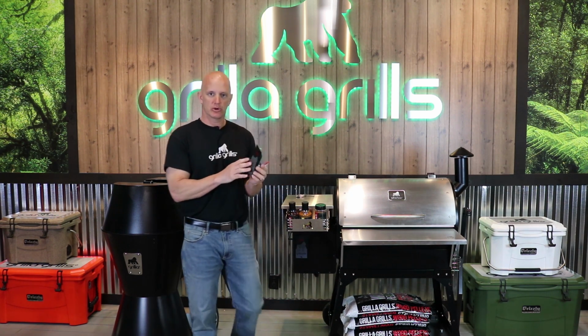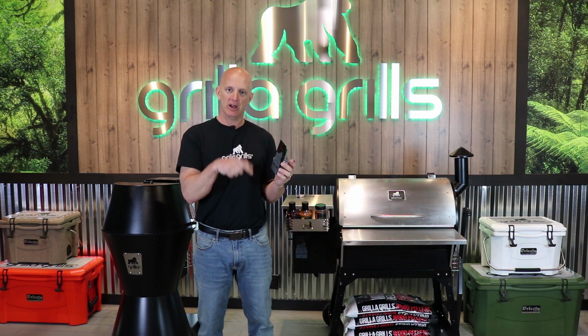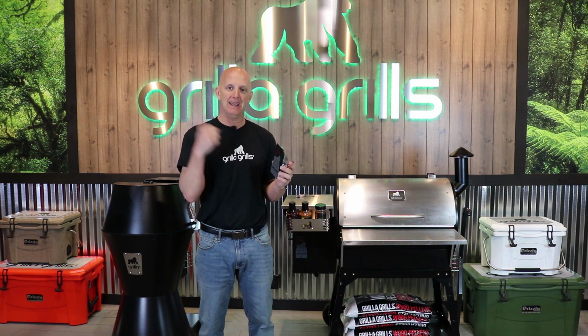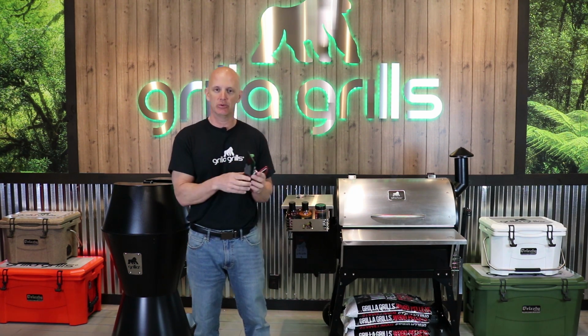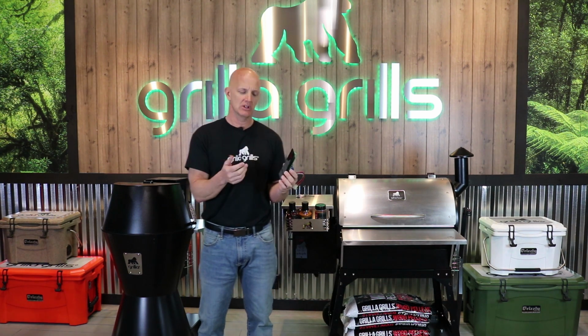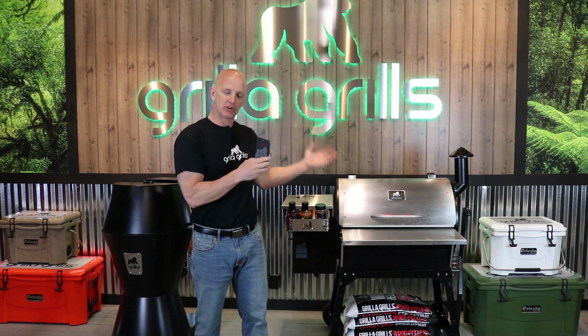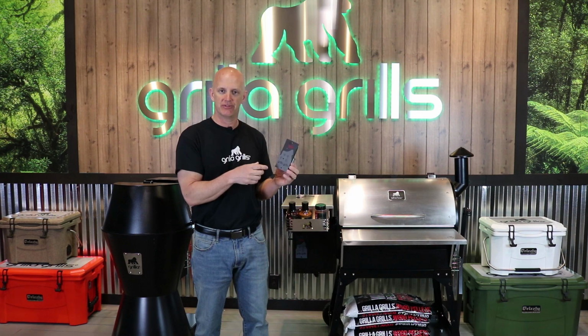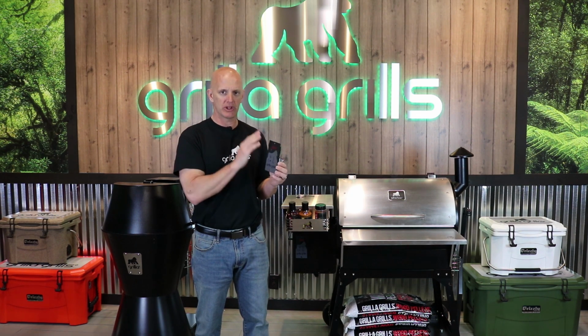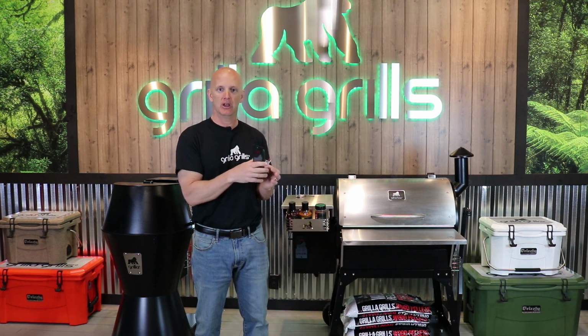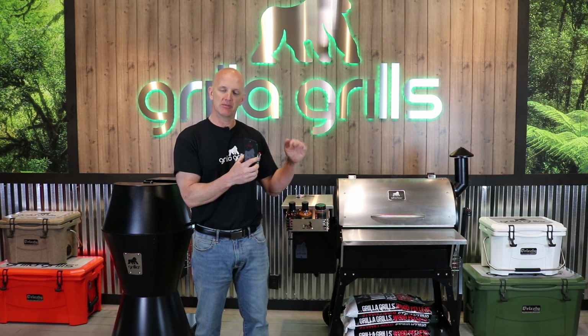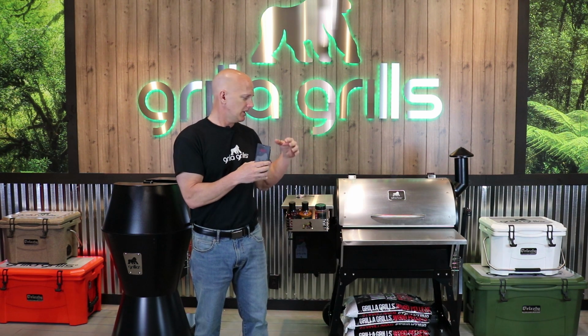Now we'll talk about the controller. There's two codes. There's an ERL, which is error low, and an ERH, which is error high. We'll start with the easy one first, which is the ERH. That means that the internal probe has reached 615 degrees. So the control board is like, I'm way too hot, something's wrong, I'm shutting you down. It'll immediately go into a cool down, which is a 5-minute cool down process, and then start flashing ERH.